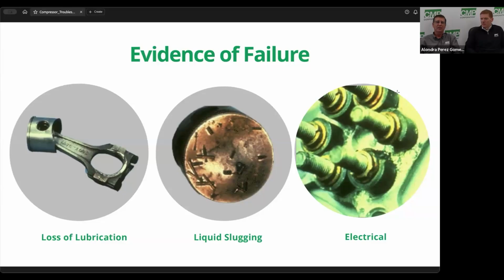If you pick one that's hanging outside the cylinder wall, which is too big for the actual piston, then you're going to have all this high compression gas there, and you just kill the efficiency of the compressor. So you always want to match that gasket up. You're going to wonder, why do I have all these gaskets that look just alike? But you want to match the cylinder wall. Yeah, exactly. That's a good one.